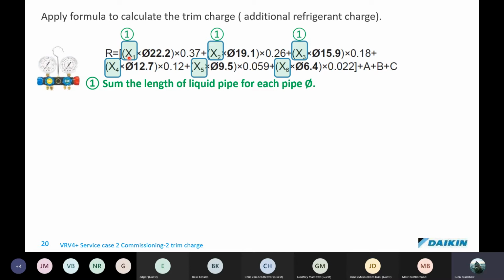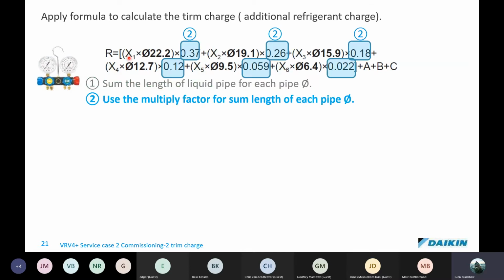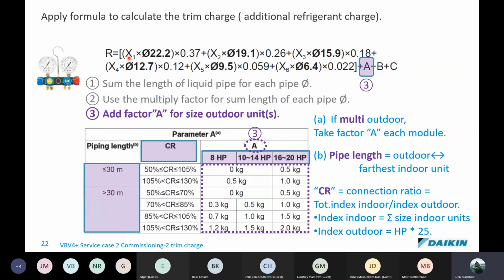Okay, and the factor is inside the installation manual. Once we calculate it by that factor, okay, it will then give us an amount in kgs of refrigerant. The next step is it may ask us, okay, now there are different formulas for different condenser units. So this example is taking us through a heat pump system. Okay, so basically we're looking at factor A, and on this one over here, it tells us that an additional amount would have to be added per condenser, or may be required to be added depending on the connection ratio.